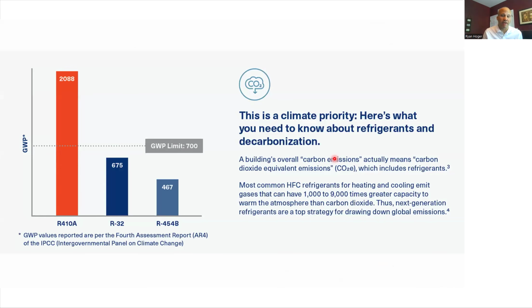The reason the other manufacturers picked R-454B is twofold. One, it is most similar to 410A out of those six they could pick from, which meant the least amount of design changes required, hence the fastest R&D for them. And two, at one point in time, they were told the global warming limit was going to be 500, in which case R-32 would not have made it. And as I told you earlier, the final limit that the EPA issued ended up being 700, so both of these refrigerants became viable. Hence the reason why you have two refrigerants to deal with in your lives.